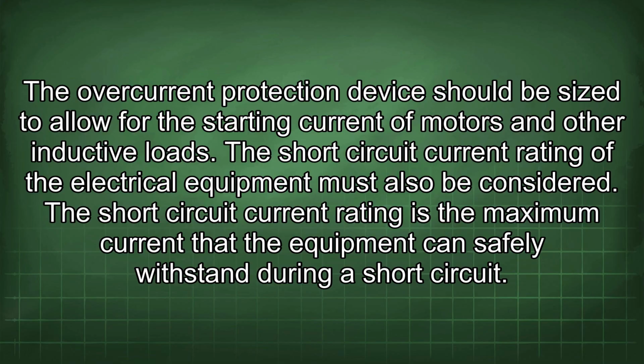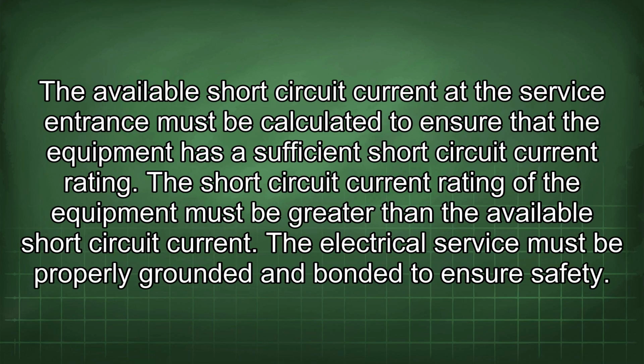The short circuit current rating of the electrical equipment must also be considered. The short circuit current rating is the maximum current that the equipment can safely withstand during a short circuit. The available short circuit current at the service entrance must be calculated to ensure that the equipment has a sufficient short circuit current rating. The short circuit current rating of the equipment must be greater than the available short circuit current. The electrical service must be properly grounded and bonded to ensure safety.